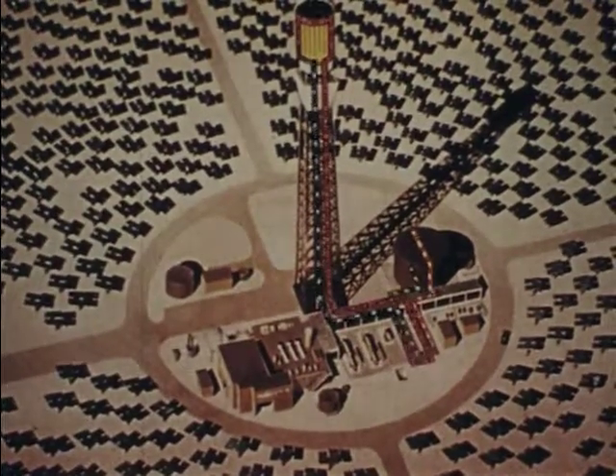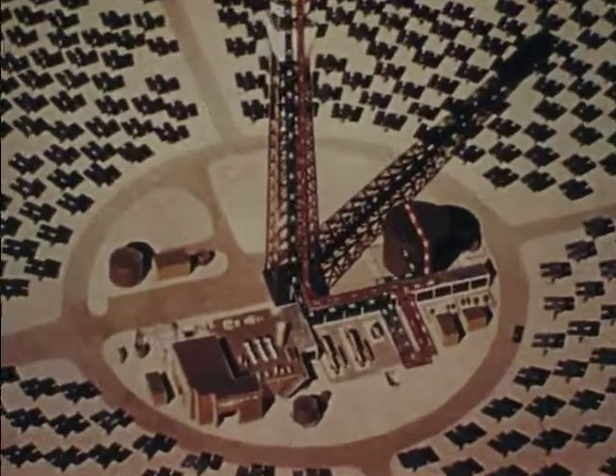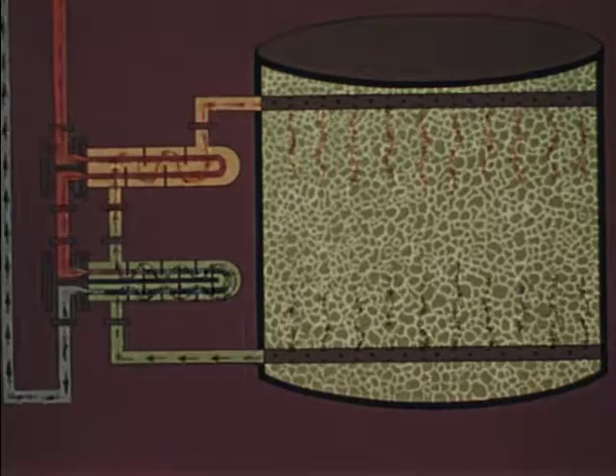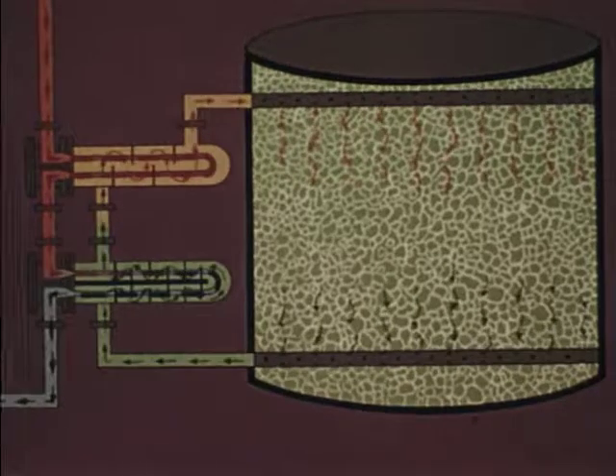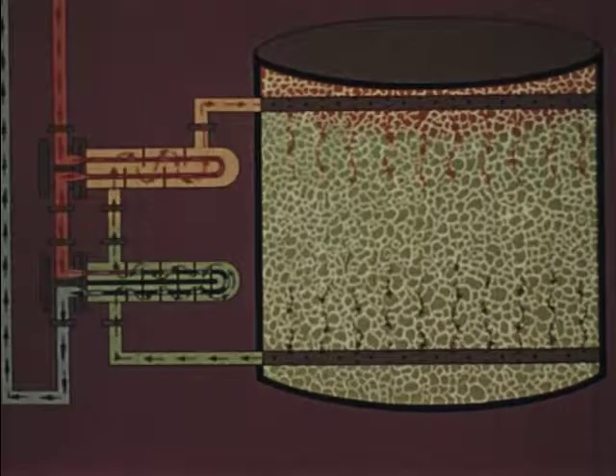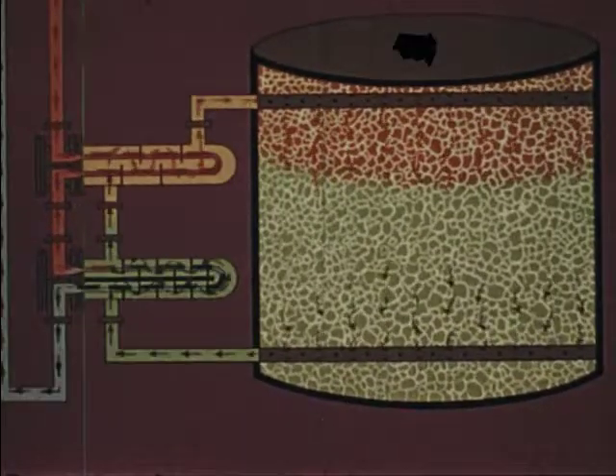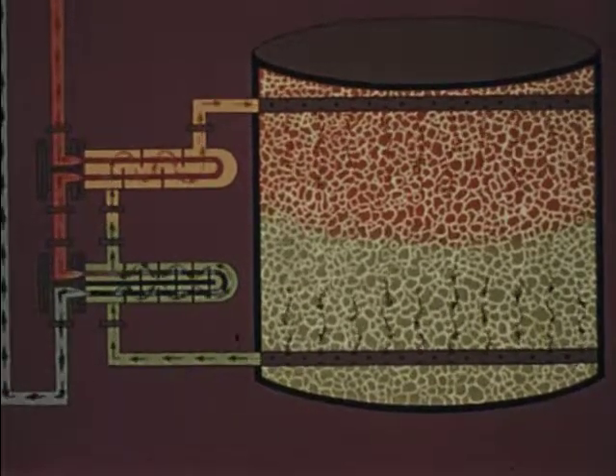The heat from the receiver may also be delivered to an energy storage system. In this system, the steam is piped to heat a stored fluid, which is pumped through a tank holding several tons of rock and sand, which retains this warmth. The colder fluid at the tank's bottom is pumped past the steam tubes, which heat it again, and then passes into the top of the tank. Over time, the volume of hot gravel increases, storing more and more energy.